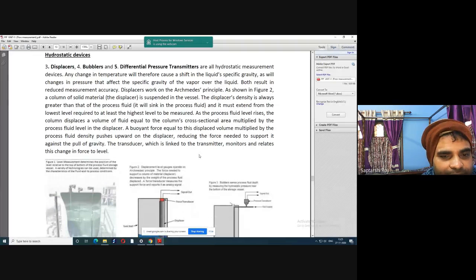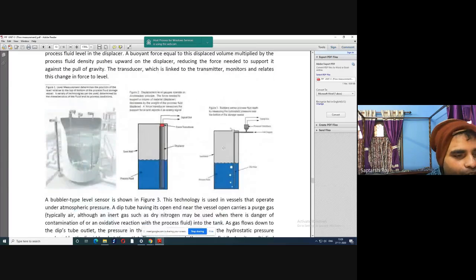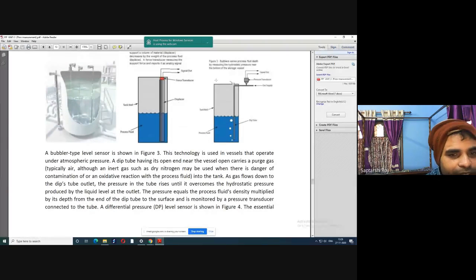As the process fluid level rises, the column displaces a volume of fluid equal to the column's cross-sectional area multiplied by the process fluid level in the displacer. A buoyant force equal to the displaced volume multiplied by the process fluid density pushes upward on the displacer, reducing the force needed to support it against the pull of gravity. The transducer, which is linked to the transmitter, monitors and relates this change in force to level. A bubbler type level sensor is shown in figure 3.